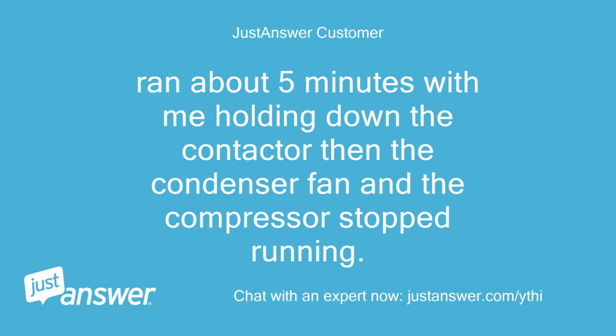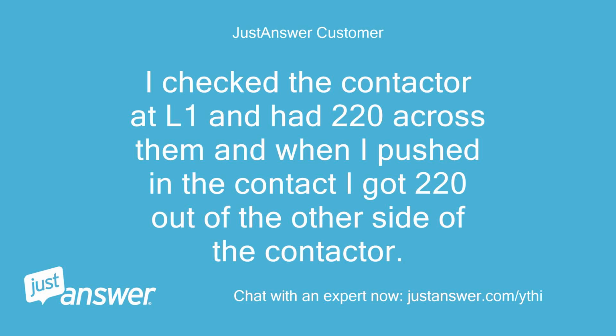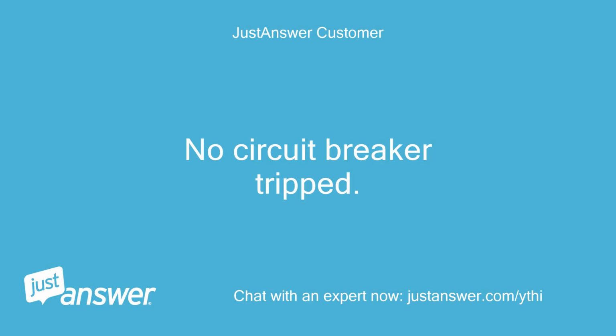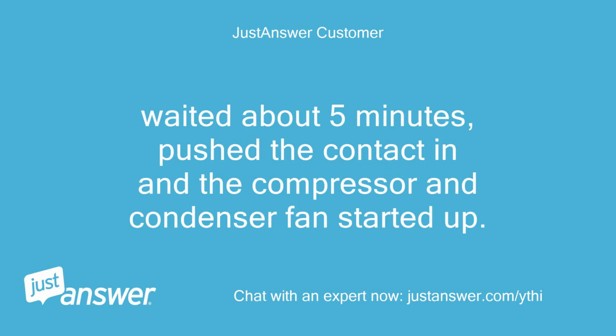Ran about 5 minutes with me holding down the contactor, then the condenser fan and the compressor stopped running. I checked the contactor at L1 and had 220 across them, and when I pushed in the contact I got 220 out of the other side of the contactor. No circuit breaker tripped. Waited about 5 minutes, pushed the contact in and the compressor and condenser fan started up.